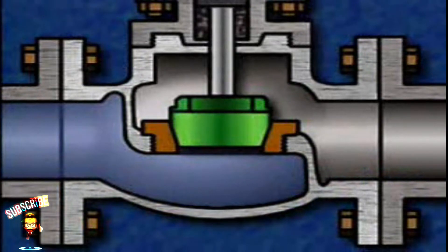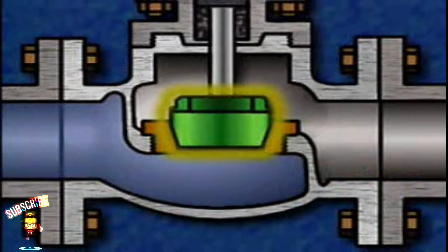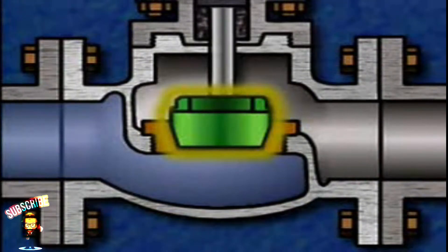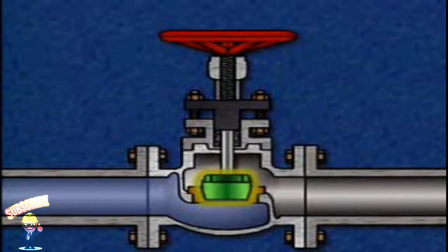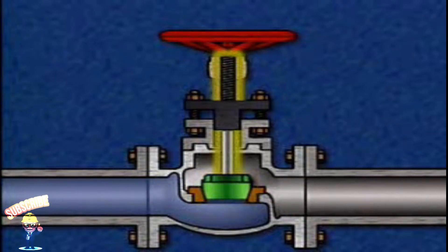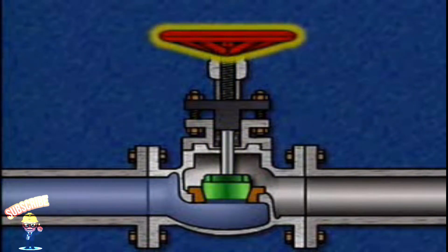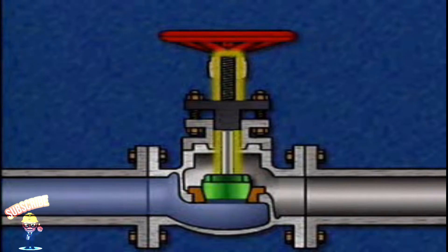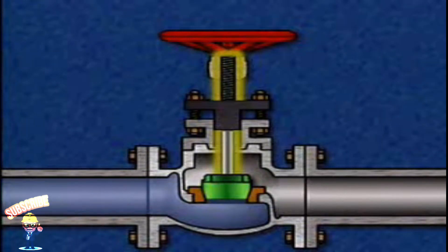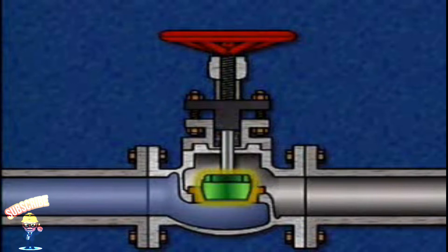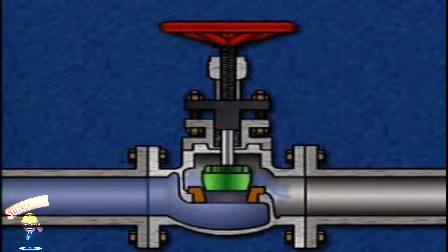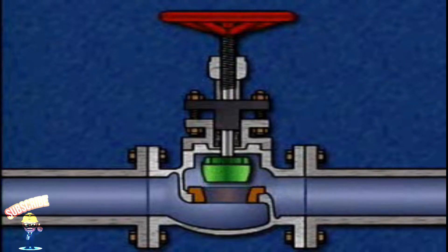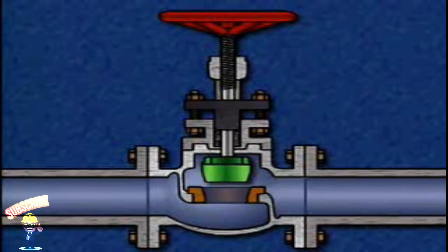The seat is used together with a movable component called a disk to control flow through the valve. The disk is attached to the stem, and the stem connects to the handwheel. The handwheel is used to screw the stem in and out, which, in turn, lowers or raises the disk. If the handwheel is turned in the open direction, the stem moves up and the disk moves away from the seat. As a result, flow through the valve is increased.